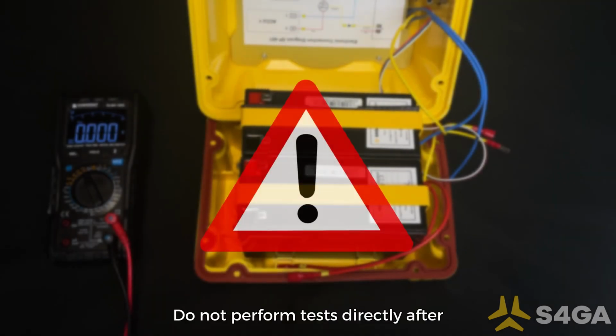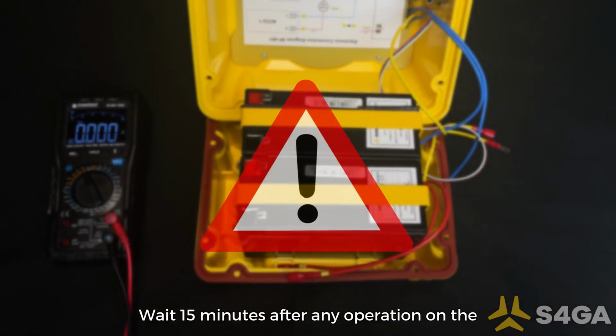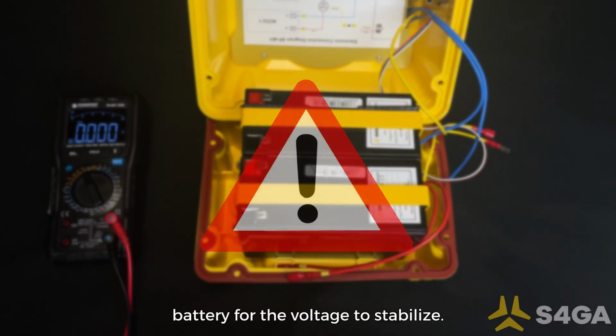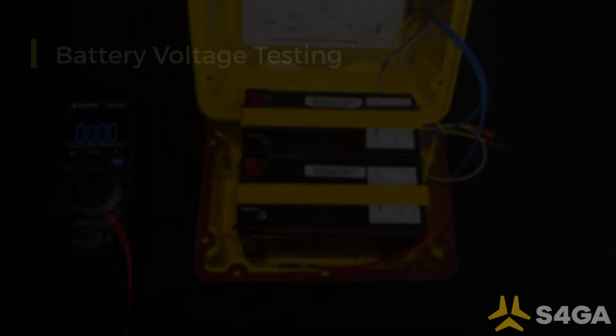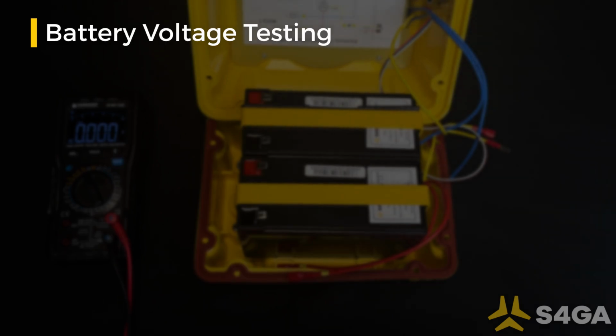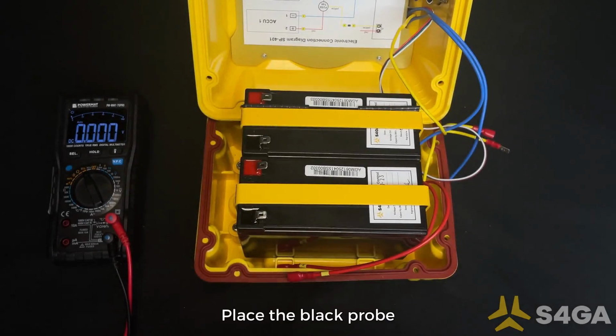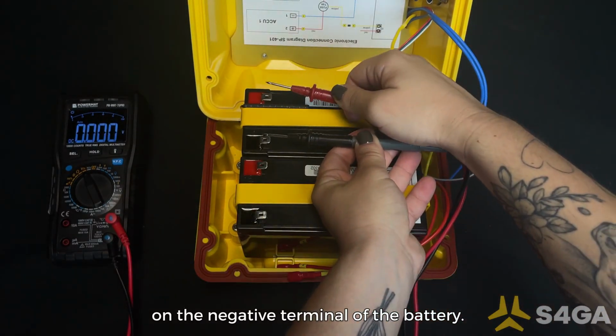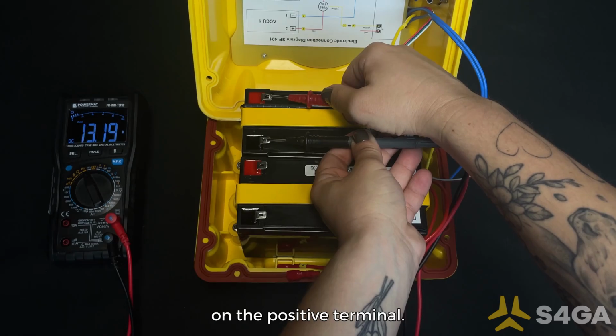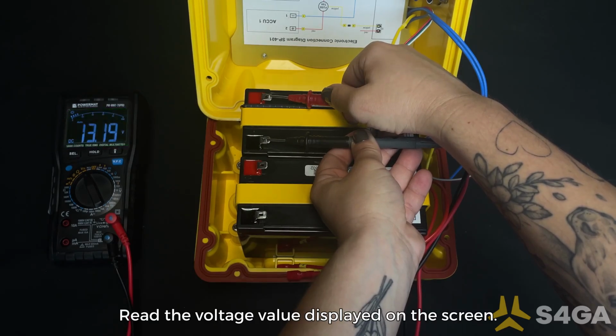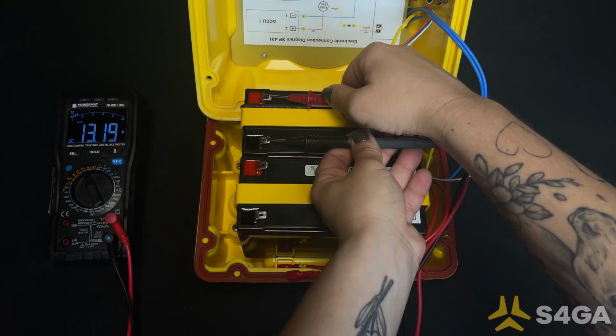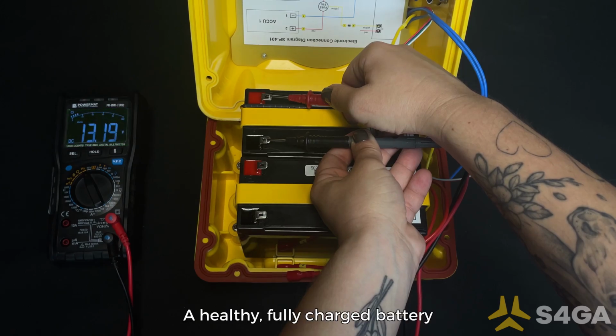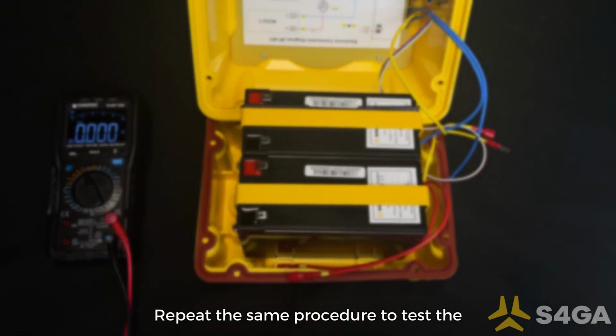Do not perform tests directly after charging or discharging. Wait 15 minutes after any operation on the battery for the voltage to stabilize. Place the black probe on the negative terminal of the battery. Place the red probe on the positive terminal. Read the voltage value displayed on the screen. A healthy, fully charged battery should read at least 12 volts. Repeat the same procedure to test the second battery in the lighting unit.